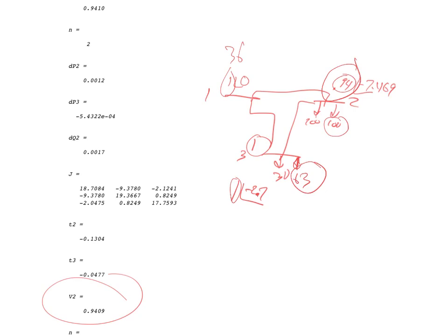Same thing with the angles. This is 0. I think this is actually in, not out. This is putting in 30. This one right here has to put in 170. So you can see its angle here is going to be slightly less than that angle because it's putting out 6 times more real power. But look at the angle here, minus 7.4. So all the real P flows in that direction.